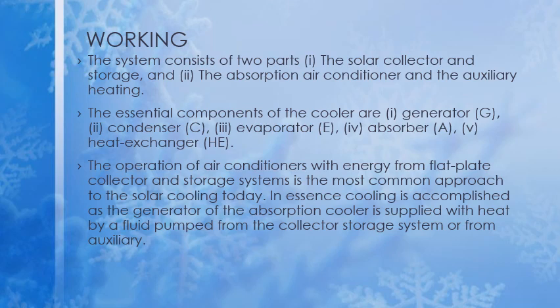The system consists of two parts. The solar collector and the storage is one thing, and the second is the absorption air conditioner and the auxiliary heating. The essential components of the cooler are generator, condenser, evaporator, absorber, and heat exchanger, which are mentioned as G, C, E, A, and HE. The operation of air conditioners with energy from flat plate collector and storage systems is the most common approach to solar cooling today. In essence, cooling is accomplished as the generator of the absorption cooler is supplied with heat by a fluid pumped from the collector storage system or from the auxiliary.